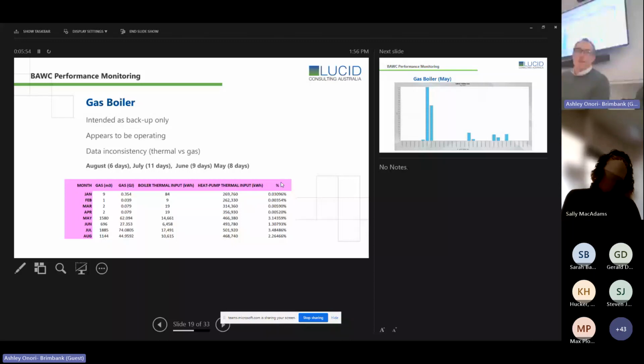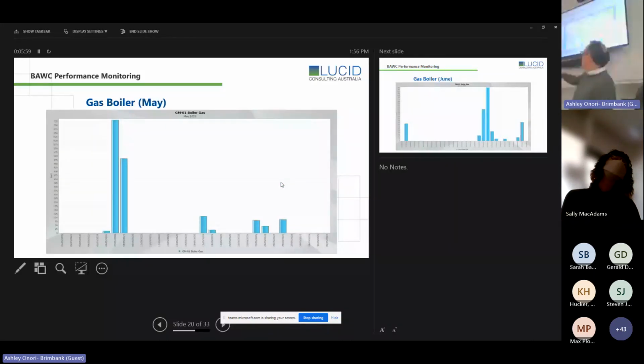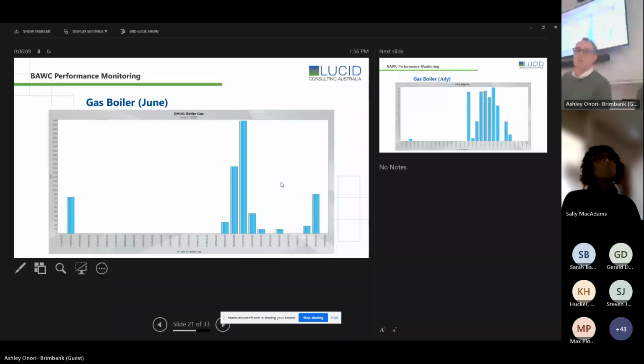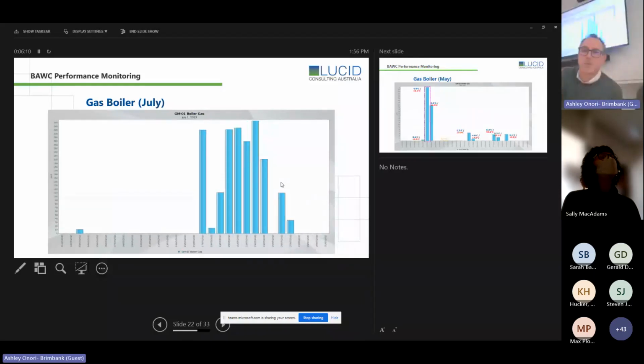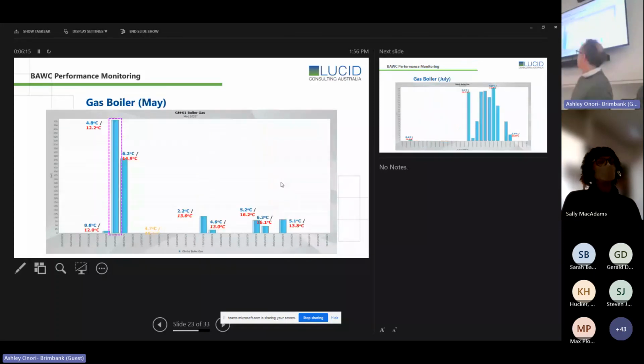This is May, so you can see the days in May. So these are the events where the boiler turned on. This is June. This is July. And then we'll just swing back to May, because what we've done is we've overlaid the ambient conditions from the BOM to illustrate when that's turning on. And typically it's kicking in where there's very low ambient, so overnight minimums in the blue, or it was just flat out one of those rubbish Melbourne days where it never gets above 13, 14 degrees. There's a couple of days where it was super cold, 4.7 degrees minimum, but the daytime temperature popped up to 18.1, and the boiler didn't kick in.